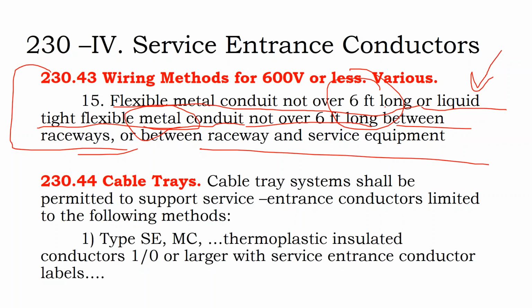That said, we had a design where we're going in through the roof cap with flex conduit, and the inverter room is located directly below. We had called for putting a box right below the rooftop for the flex conduit to land in, at which point we would transition to EMT and dry rated wires. The client said, well, I'm doing this as a self-install. I'd rather spend more money on material and less money on figuring out what to do. Can't we just run these flex conduit runs directly down into our battery room? That was about 10 feet between the roof deck and the battery room. Your flex conduit run should be not over 6 feet long for your service entrance conductors. So, technically, no, that would be a code violation.